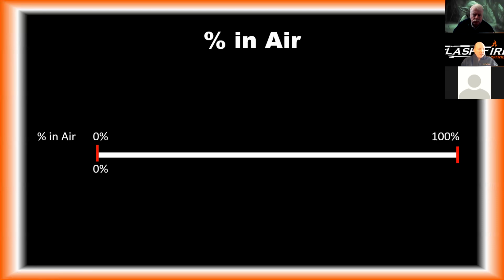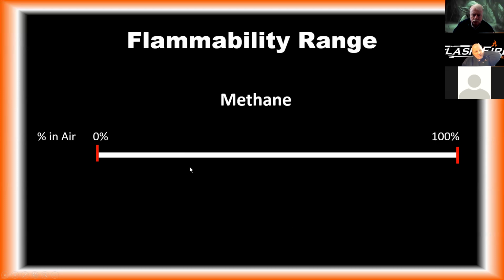So when we talk about percent in air, we could have 0% in air, we could have 100% in air. We know that our oxygen level should be 20.9, 20.8, depending, okay? So that's where our oxygen level is, 1/5 of the atmosphere. Our O2 sensor should be reading 20.9% in air. When we talk about the flammability range, this is not how our meter is reading, but we have 0%. We could have 0% of natural gas in air, or we could have 100% of natural gas in air, right? So we could have 0 or 100%.